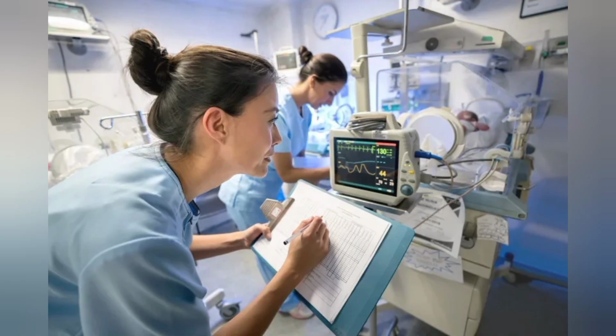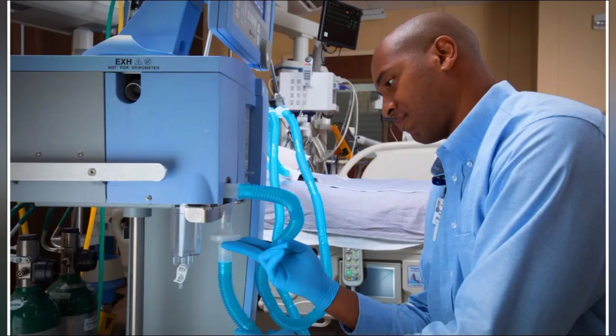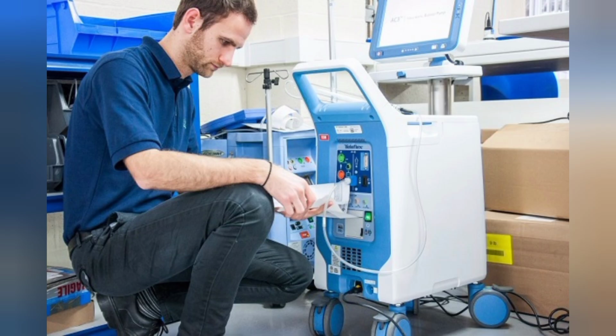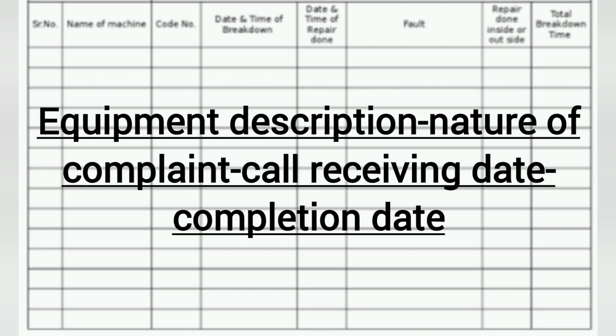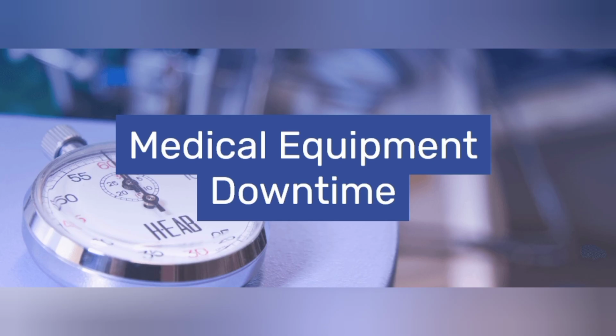Then the seventh file is the breakdown register. For every breakdown call of equipment, a service report should be made. Whatever work has been done on the equipment, either by an internal biomedical engineer or by a company engineer, the service record should be there in the service report form. These service reports must be attached in the breakdown file, and whatever breakdown calls are received in the biomedical department get entered in the breakdown register. The register will reflect equipment description, nature of complaint, call receiving date and completion date. This register will track downtime or uptime of equipment.